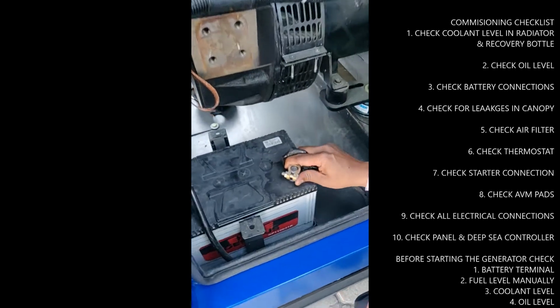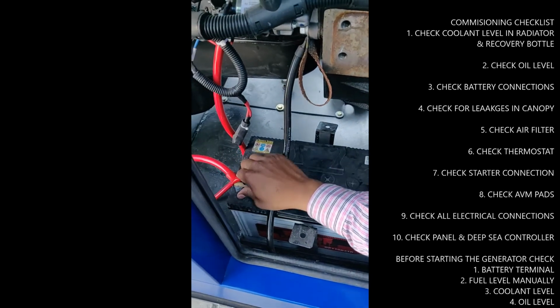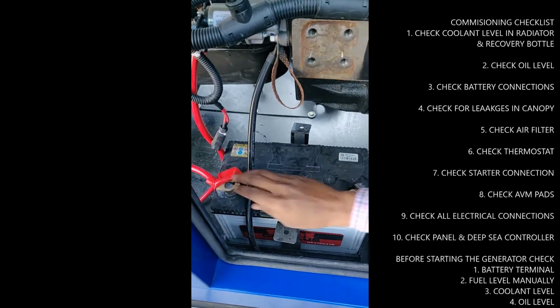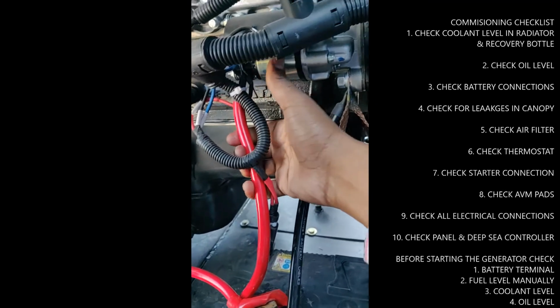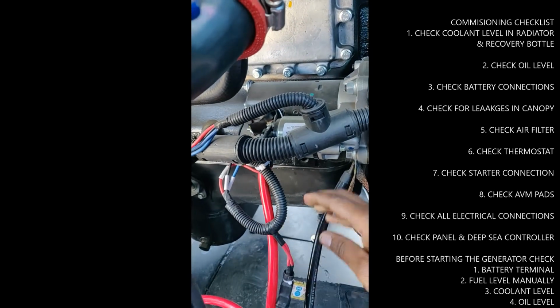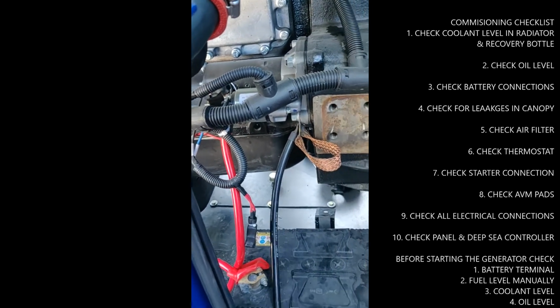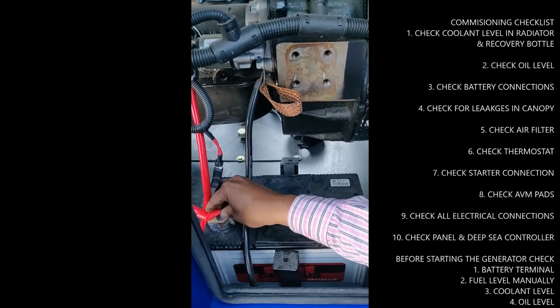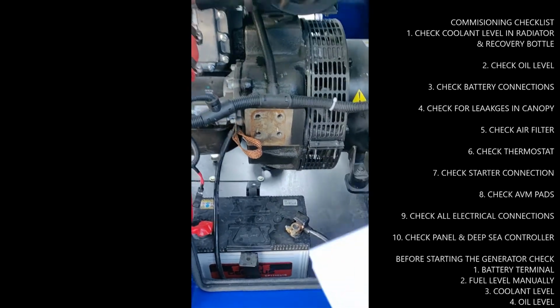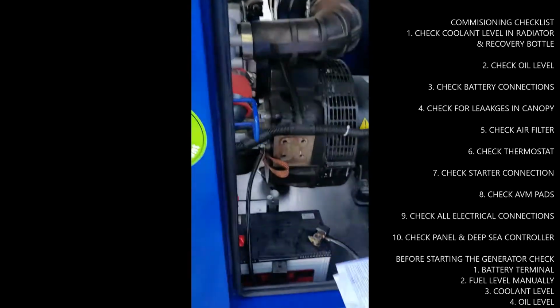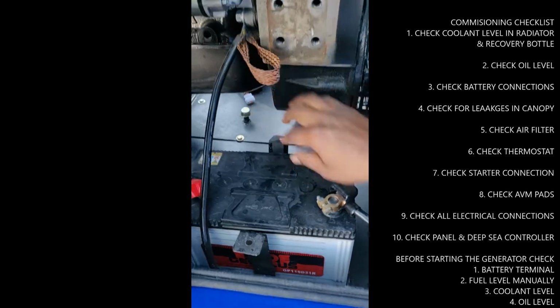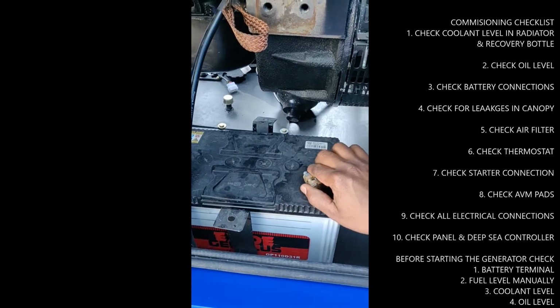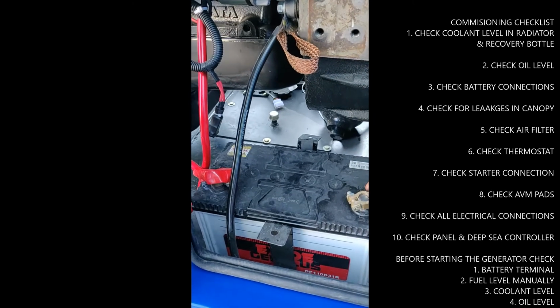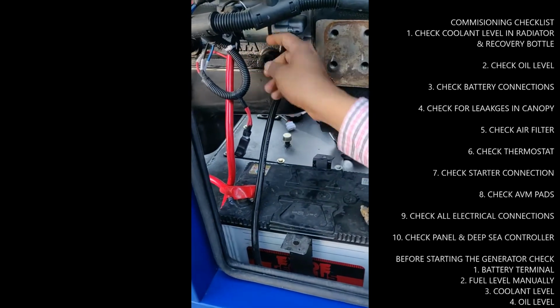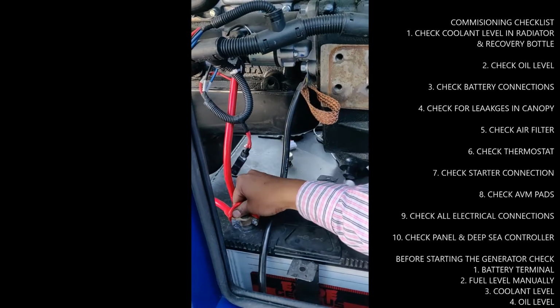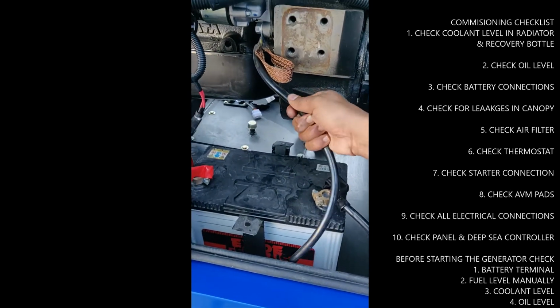Now we come to the battery connections. It is very important to check the battery connections. Red cable denotes the positive end, which is connected to the starter motor. Black cable denotes the earthing, that is the neutral, which goes to the body of the generator. Red cable, the positive terminal, is attached to the self starter, and black cable, the neutral cable, is attached to the body of the genset. Here you can see the same. This is the starter, and the starter is connected with the red cable, and the black cable of the terminal is connected to the body for neutral.